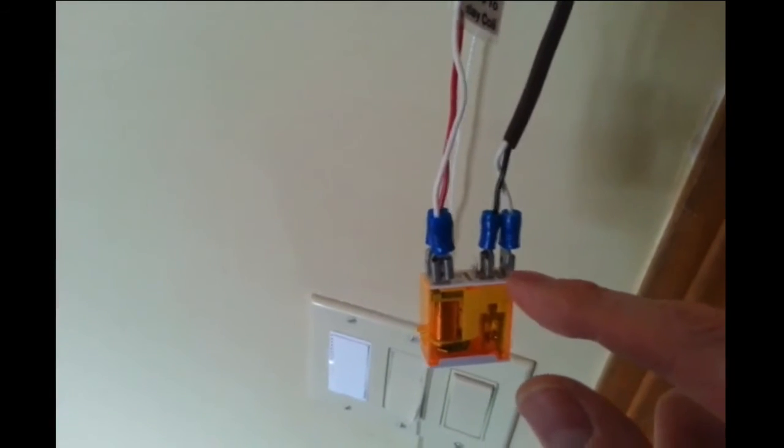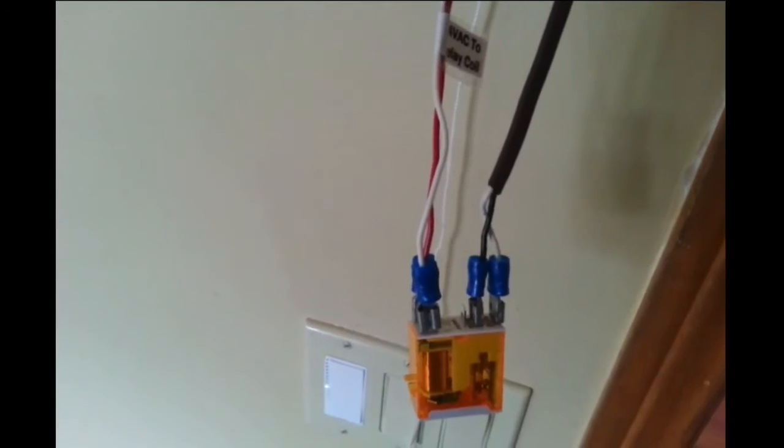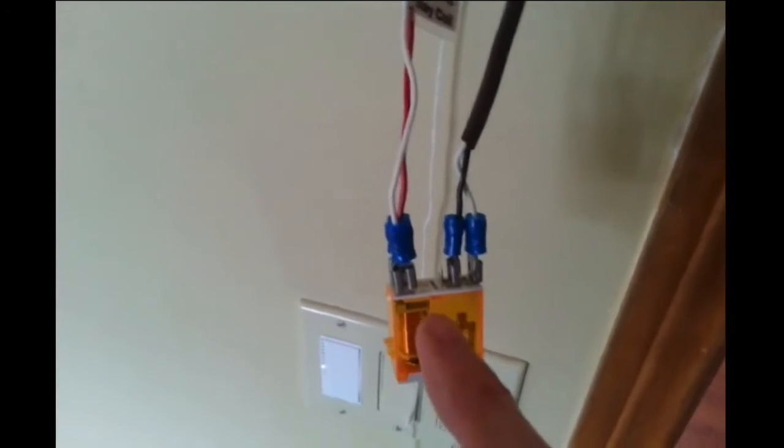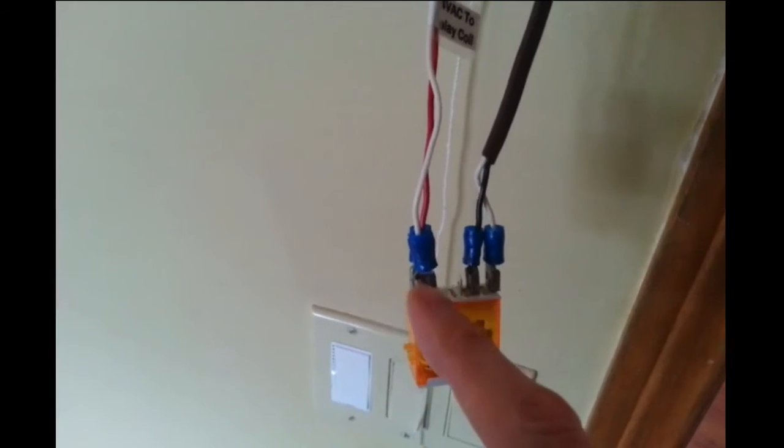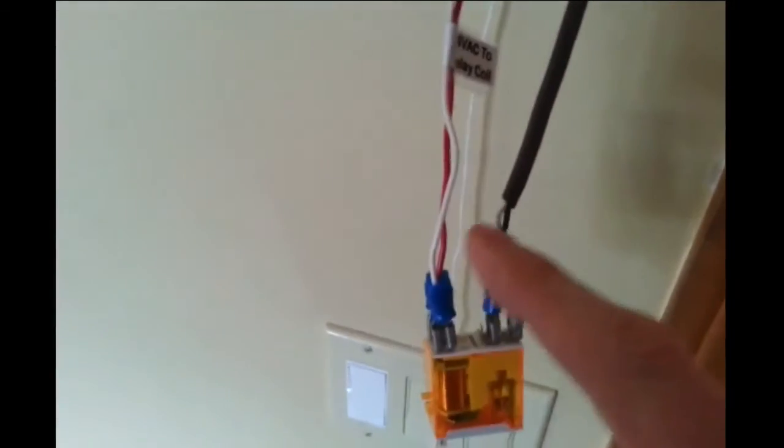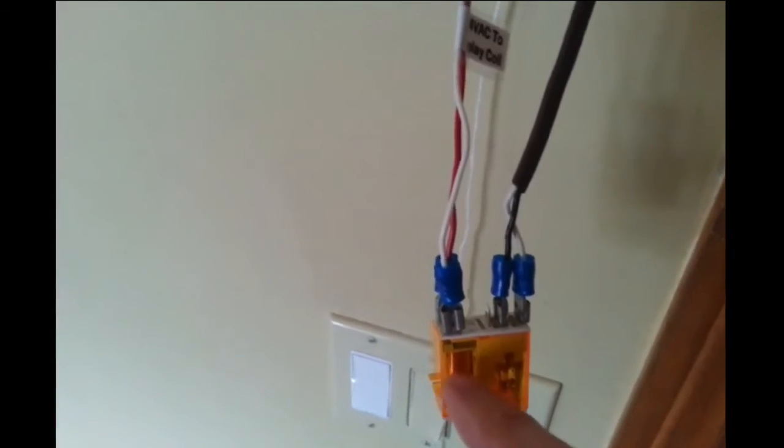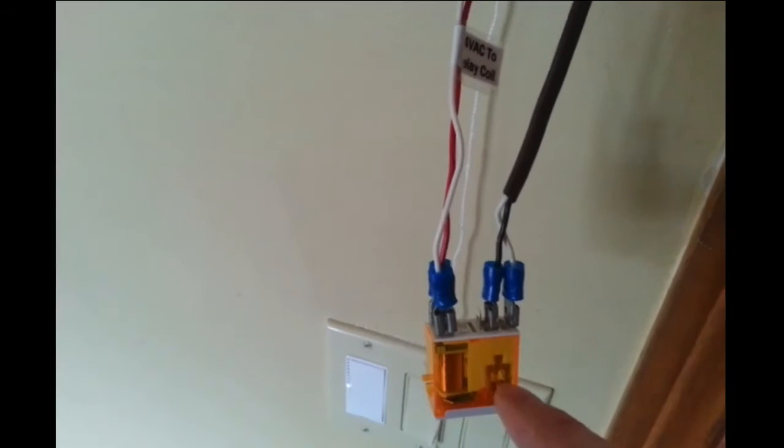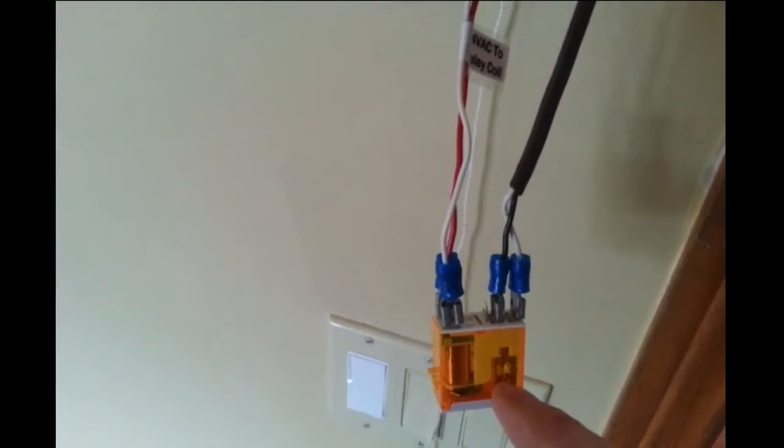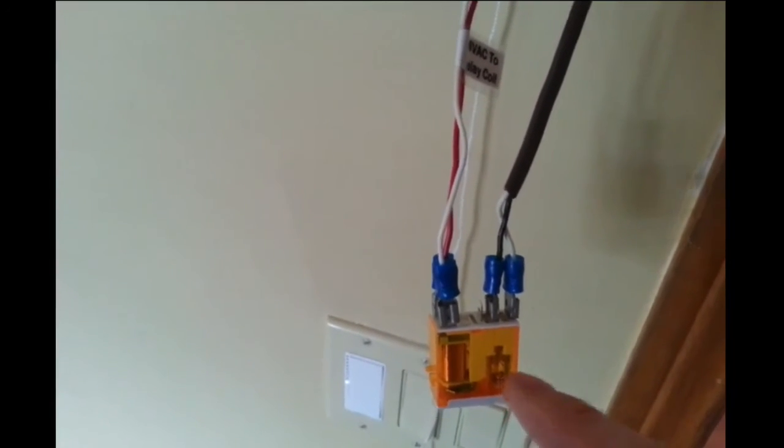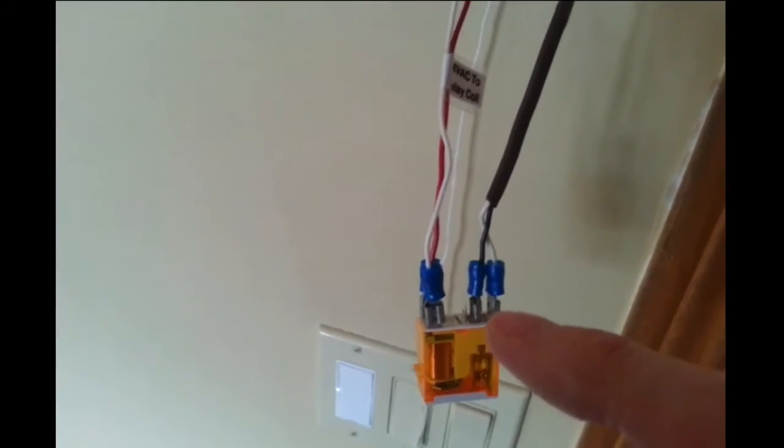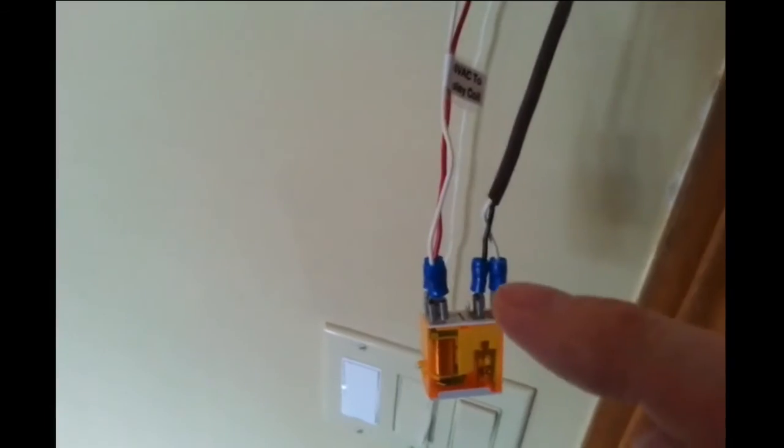So normally open means it's not going to be running unless it's called for by the coil. When the coil is energized from the thermostat, 24 volts gets fed down to here, which energizes the coil and closes the normally open contact. This shorts the circuit between these two switches and allows the millivolt to go through there, turning on the fireplace.